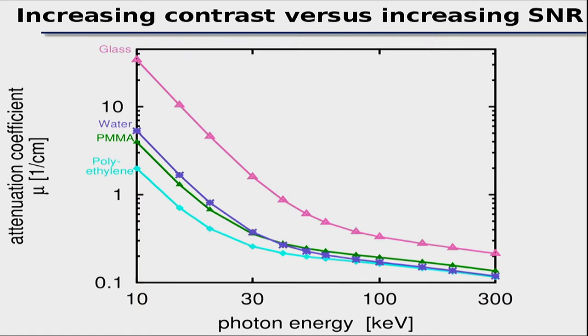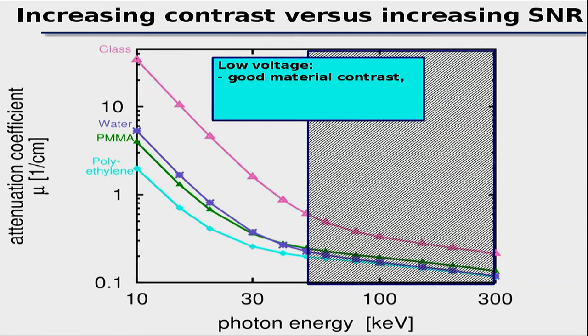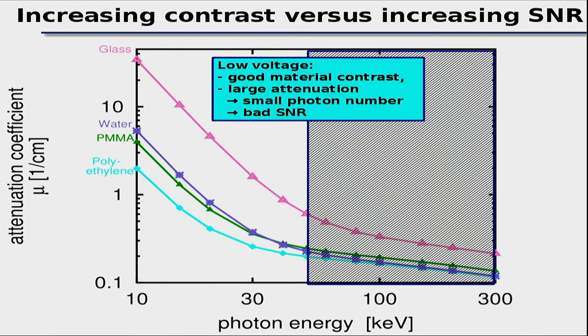When choosing acceleration voltage, there is a fundamental trade-off. At low photon energies, material contrast is high — the attenuation curves are well-separated — but overall attenuation is large, so few photons reach the detector and SNR is poor. At high energies, attenuation is low and photon count is high (good SNR), but the curves converge and contrast between materials decreases.